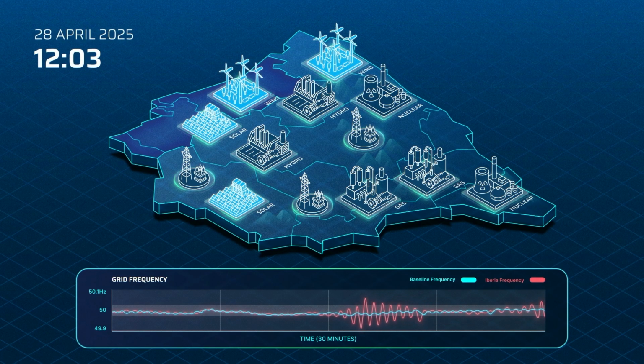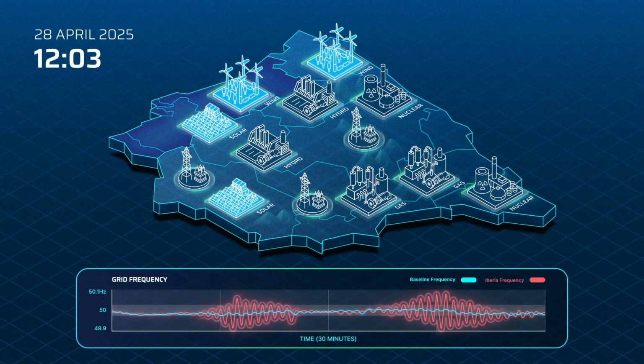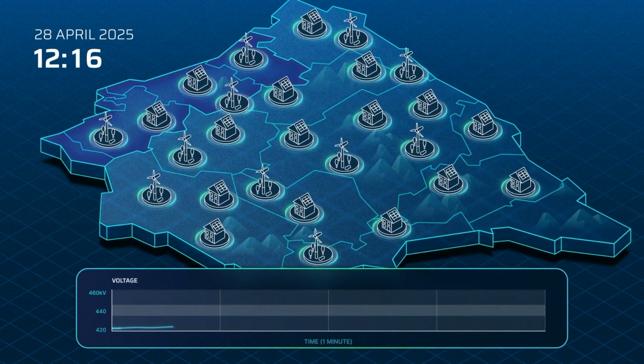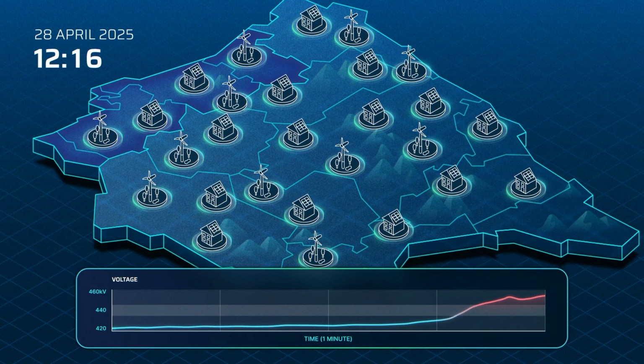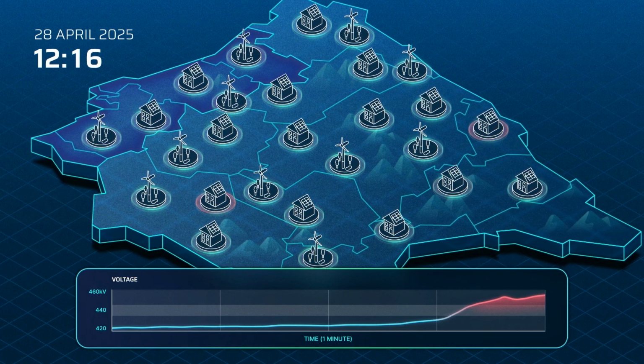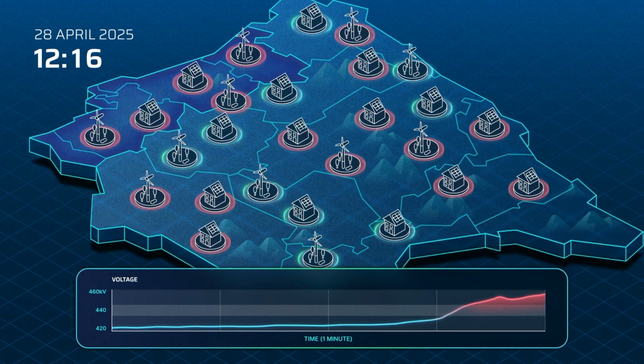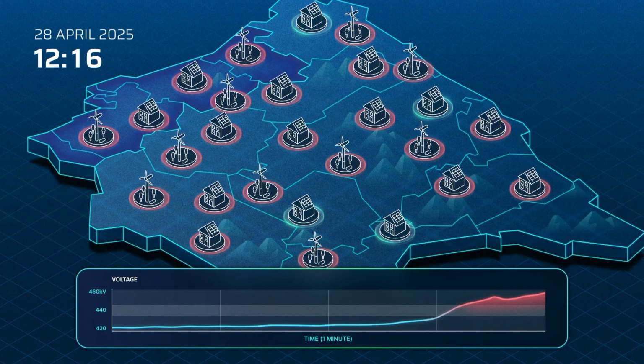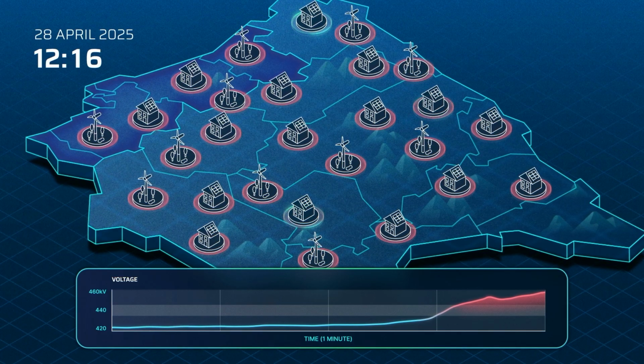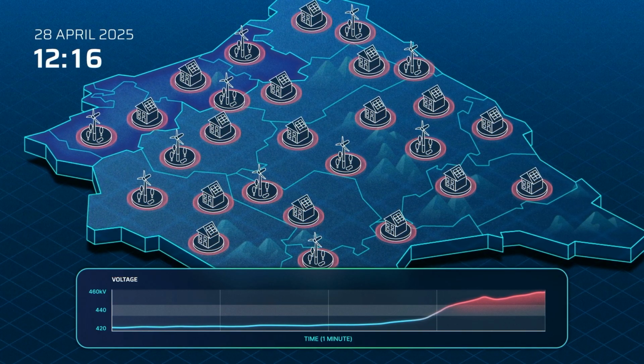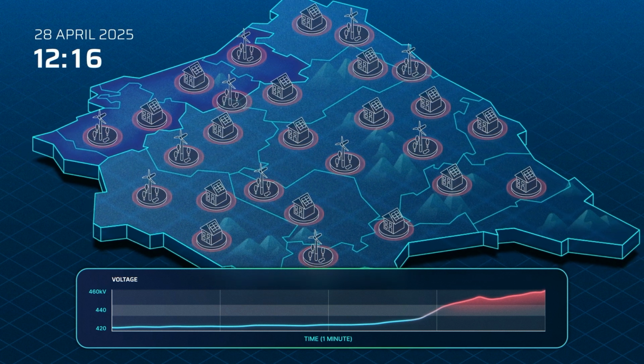On the day of the blackout, warning signs appeared at 12:03 when subtle power oscillations were detected across the border. By 12:16, these oscillations began knocking small distributed energy resources offline. Across the peninsula, local rooftop solar and municipal wind turbines detected a massive voltage climb, protectively disconnecting and rapidly worsening the surge.